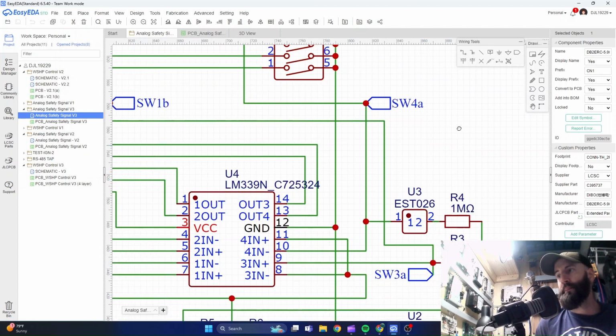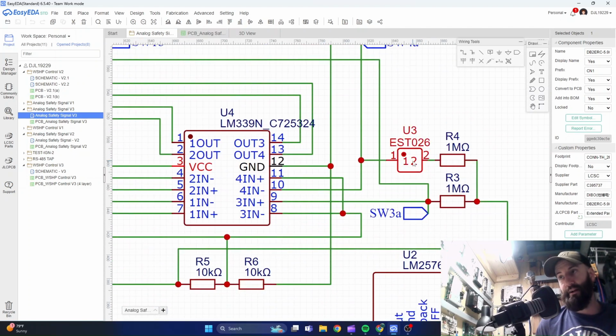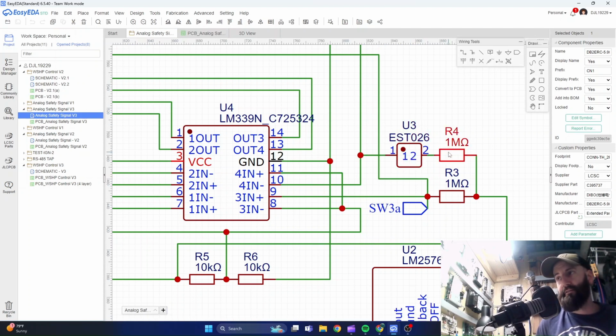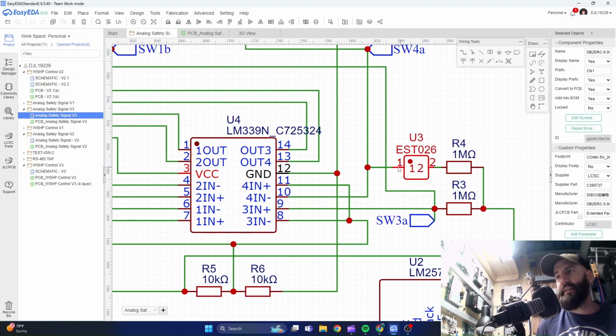Now what's going to happen either in a test state when we switch this safety here to ground, then it's going to be pulled low. Or if this can find a path back to ground through the conductivity of the condensate, either to the ground probe that you've put in or to the stainless condensate pan that's grounded, if it can find a path back that's able to overcome this 1 mega ohm resistor, which isn't difficult, if it can find that path back through the condensate, that's going to pull this below the 2.5 volts. It's going to pull it to 0 or practically 0, close enough to 0 that it's going to be below this 2.5 volts we have coming in here. That's going to make output 4 go high.